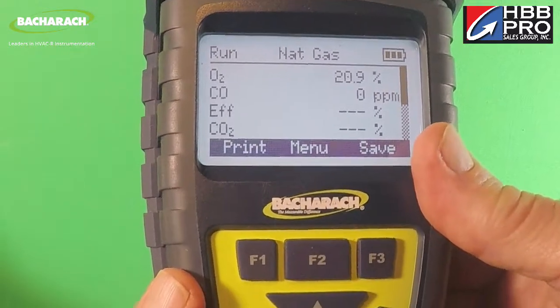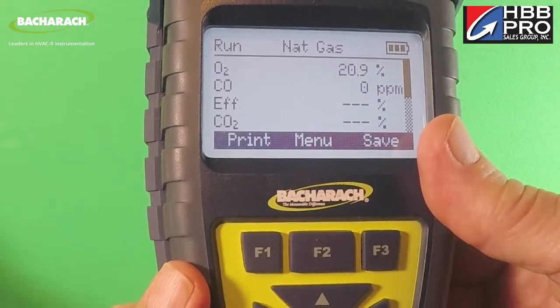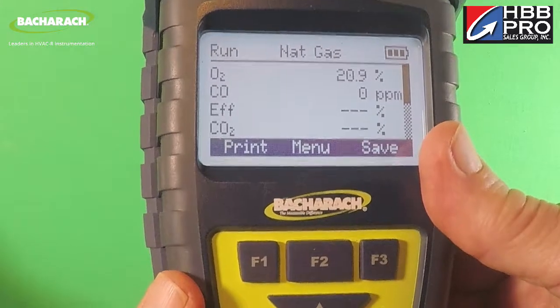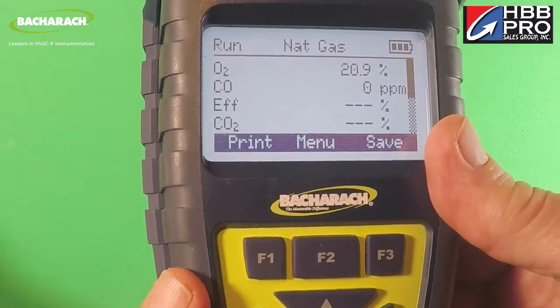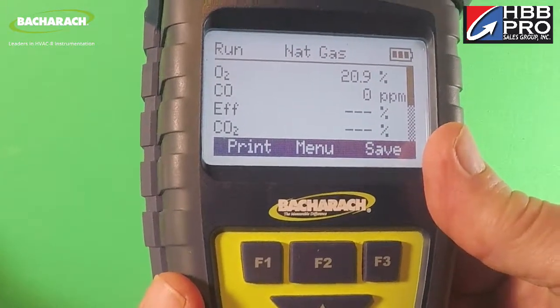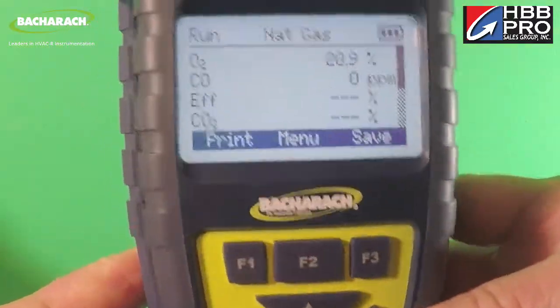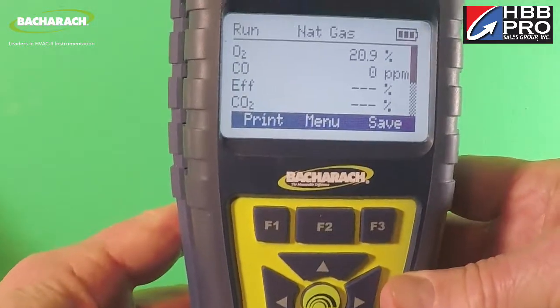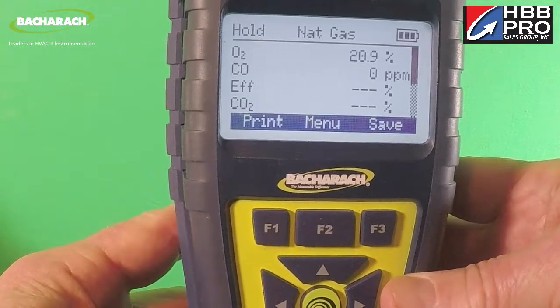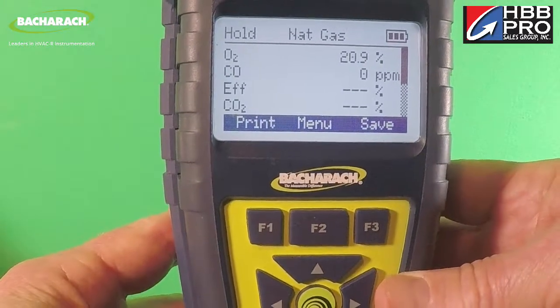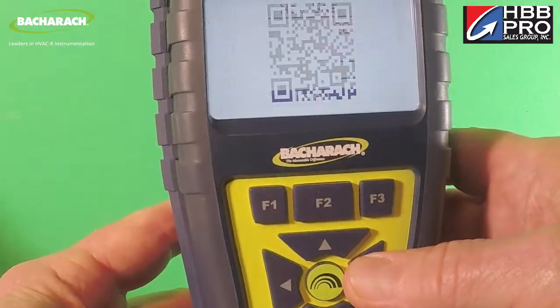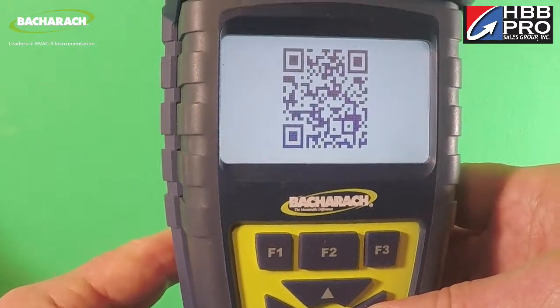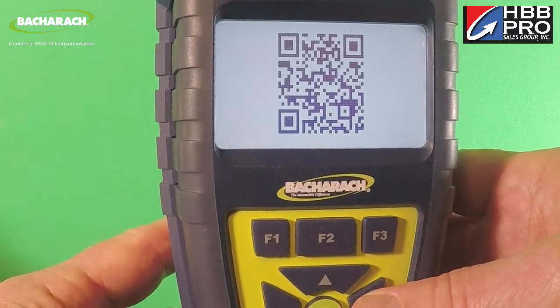Finally, and most importantly, remember to download the Bacharach reporting app. It's pretty amazing. I'll cover this in depth on another video. Definitely check it out. What you do is you bring up the test results that you want to document. Let's say we've got some test results here we want to document. You hit the run hold button to turn the pump off and lock the screen. Then you press the scroll right button. A QR code will come up in the display.